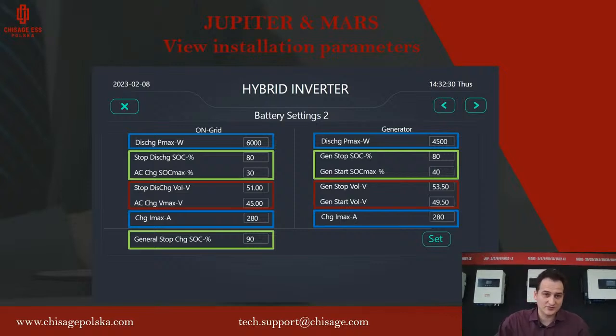Stop discharge state of charge, so stop discharge SOC, means the percentage at which the inverter has to stop discharging the battery. For example, now it's 80, so the inverter will stop discharging when the battery reaches 80%. AC charge SOC is the SOC at which the inverter charges the battery from the grid. Now it's 30, so if the battery is lower than 30, the inverter will charge the battery from the grid. If it's higher than 30, only from PV.